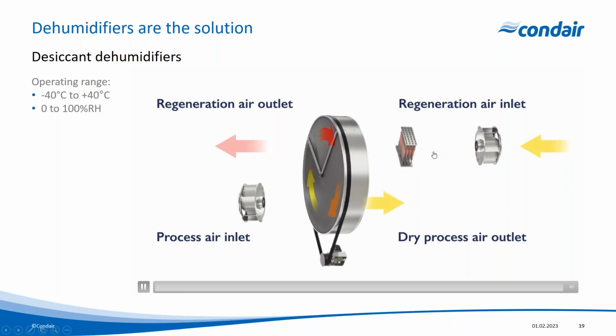we duct it through a fan and then through a heater. And we're going to heat that air up to maybe 120 degrees C. And we put that warm air over a section of that rotating rotor. And that air then dries that section of the rotor out. And we have wet regeneration air, which we then duct out to ambient. So we're capturing the moisture on this side of the desiccant wheel, but as it rotates into the much warmer airflow, that moisture is released.